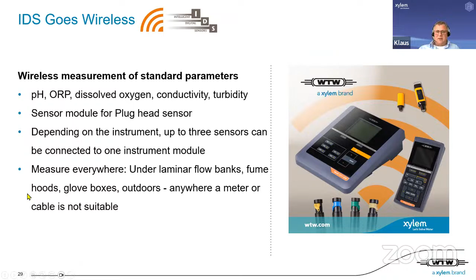You can see here below, and then we can measure, depending on the meter, up to 3 sensors at one instrument. And it's useful because you can measure everywhere where you do not want to have a meter. For instance, under a laminar flow bench, people normally don't want to have a meter when they're measuring pH under a laminar flow bench. Also when measuring under fume hoods, everywhere where you never want to have a meter, this is a good solution, because you can place the meter outside and do the measurement inside of this fume hood or whatever. And how does this look in detail, a little bit closer?